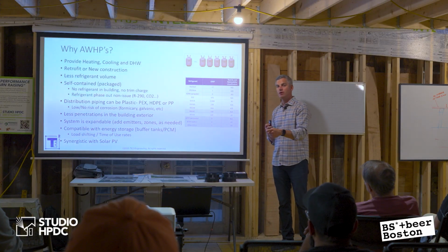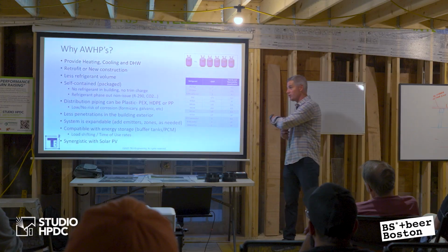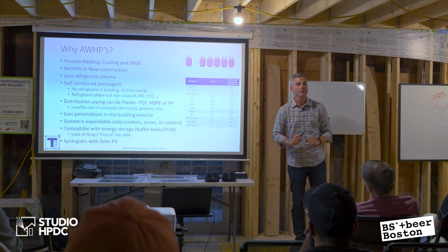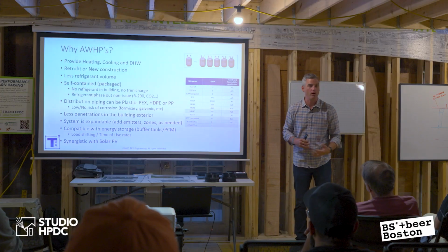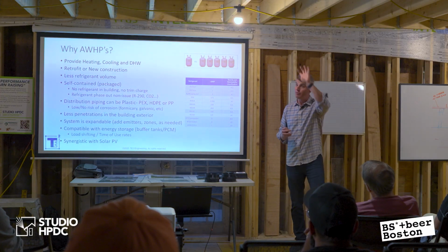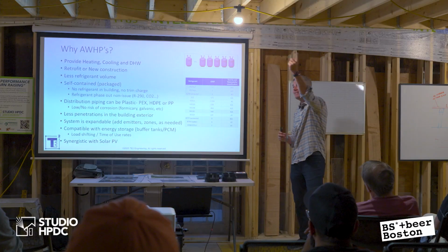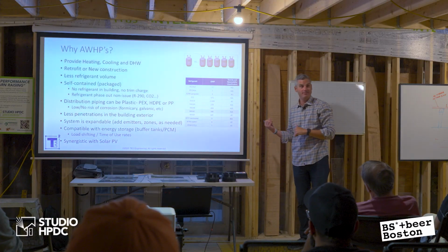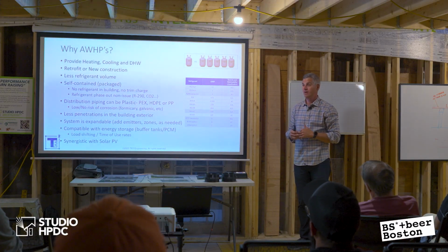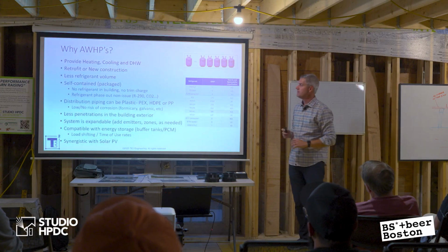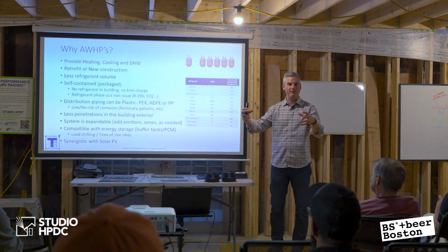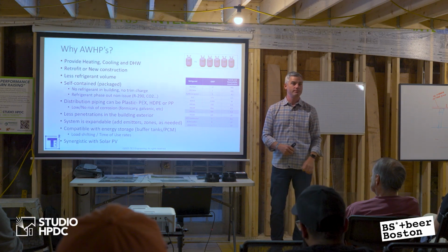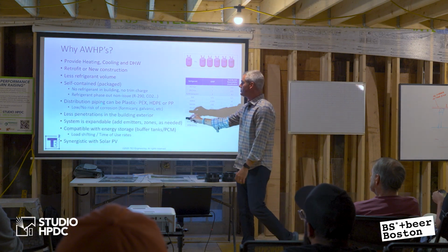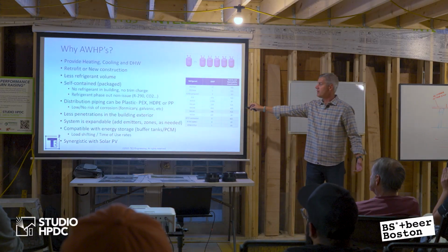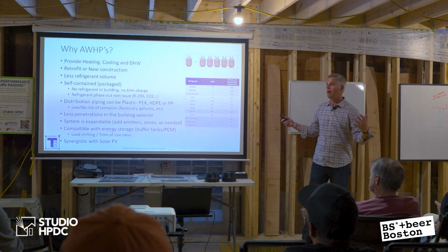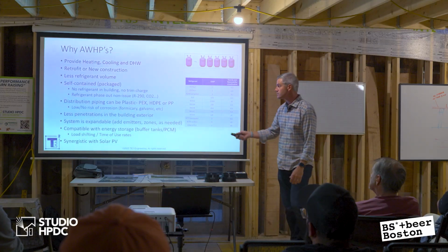So I have a brand new system going in a house. Let's say it's a 410A system, split, outdoor unit, indoor unit, refrigeration lines in between. My air handler, let's say, fails. I can't get a part. You're telling me that I have to replace the indoor unit, the air handler, the line sets potentially, and the outdoor unit? That's a problem, right? Sometimes you can reuse the line sets, sometimes you can't. I don't have that issue. My air-to-water heat pump fails, I rip the box off, I put a new box on. Okay? Distribution piping can be plastic. I can use PEX, high-density polyethylene, polypropylene. I can use copper. I can use any piping material that carries water, no problem.